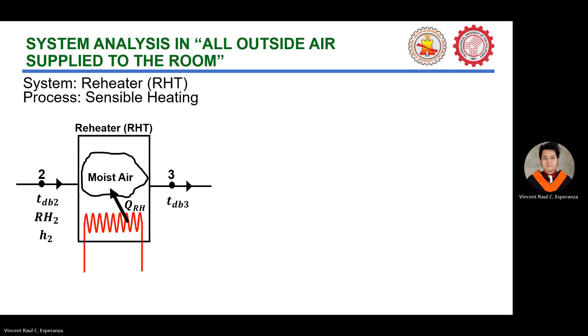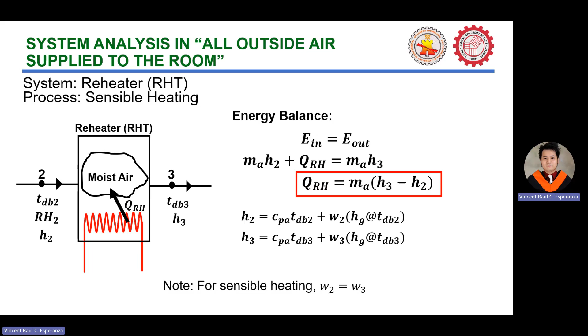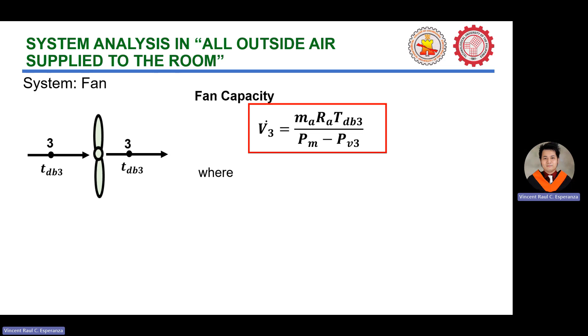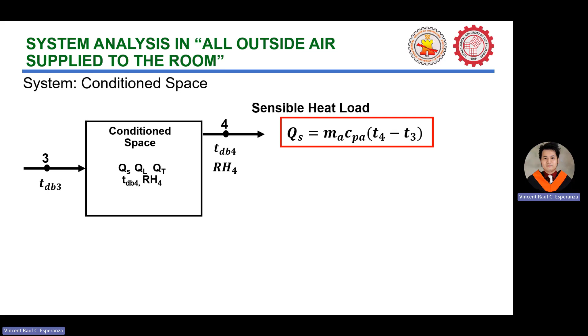Ayan. And by energy balance, energy in is equal to energy out. Then we can see that the heating load is equal to the mass of air times the difference of enthalpies, H3 minus H2, wherein H2 and H3 are defined. And note, for the sensible heating, W2 is equal to W3. Okay? Then, yung fan naman, syempre, meron tayong fan capacity. Ayan, nanggaling ito sa PV equals mRT, where V is the volume flow. And lastly, we have the conditioned space. Ayan, pinakita ko kanina: the sensible heat load, the latent heat load, and the total heat load.